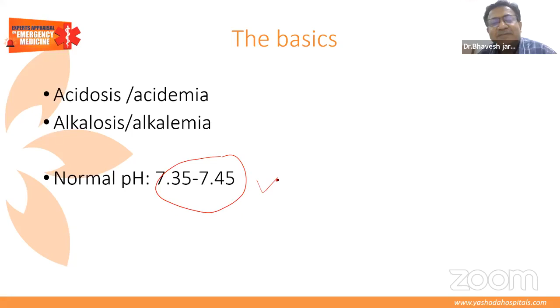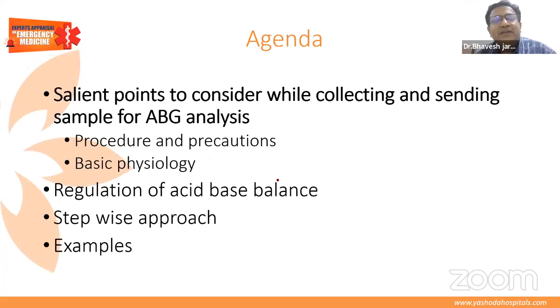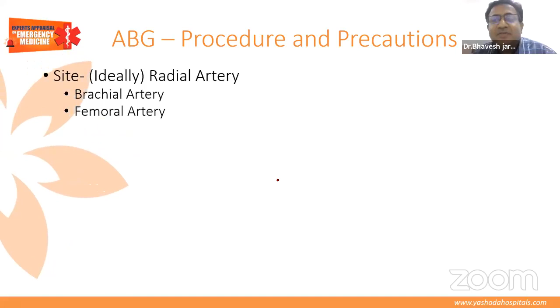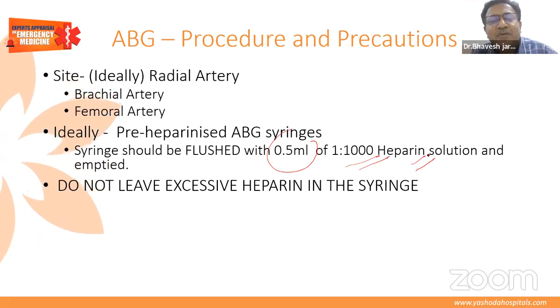Now, a pre-heparinized ABG syringe is used, and the salient feature about this is that you should flush it with 0.5 ml of 1 in 1000 dilution of heparin. If you don't flush it and keep it inside, like say you are still having 0.5 ml of heparin in the syringe, then the sample gets diluted. So do not leave excessive heparin in the syringe. Because of the more volume, if you are not flushing it out, there is a dilutional effect, and that dilutional effect will decrease the bicarb level and PCO2 level as well. So your reading will not be completely accurate. So always have a syringe that is 2 cc and have a blood volume of 0.5 ml, flush the syringe, pre-heparinize and flush it completely. That's an important thing.